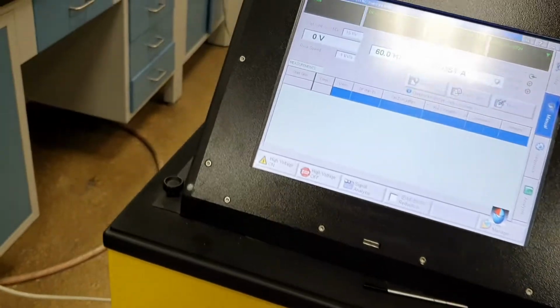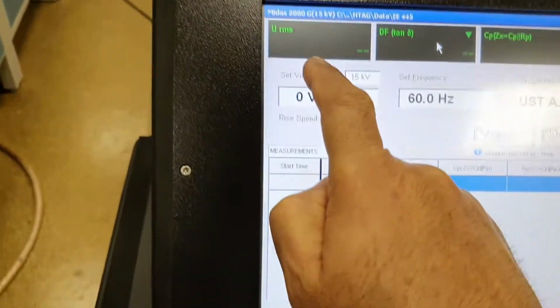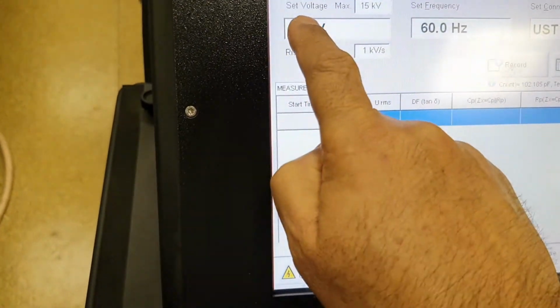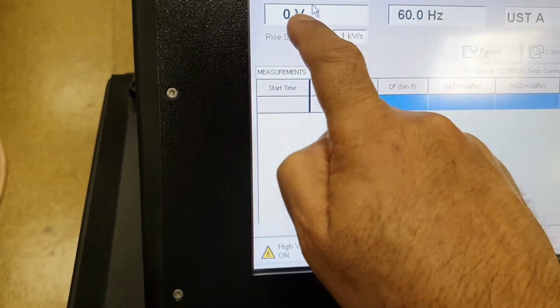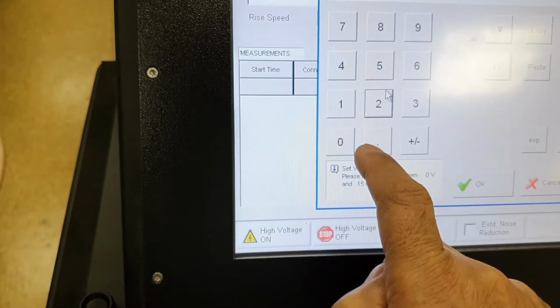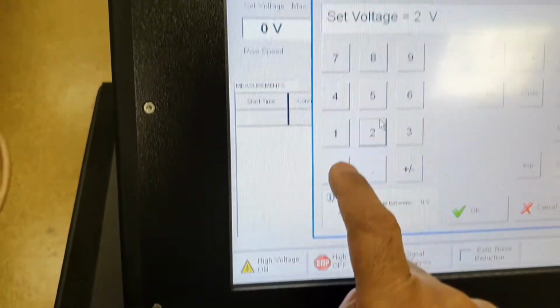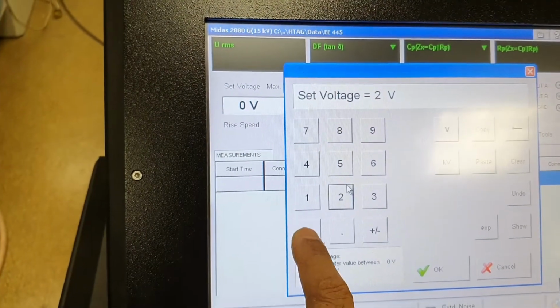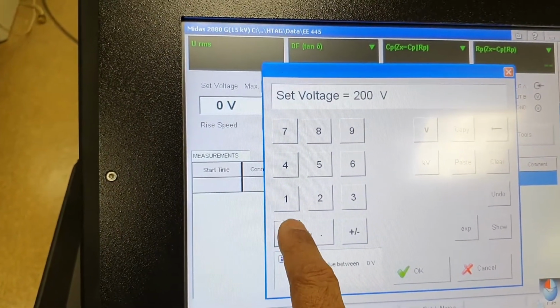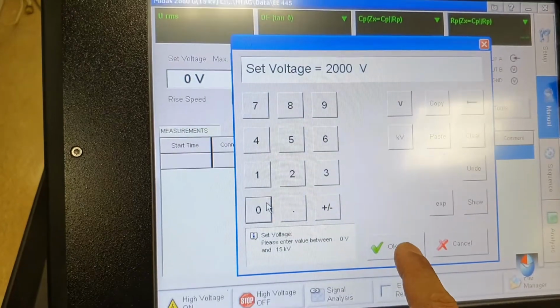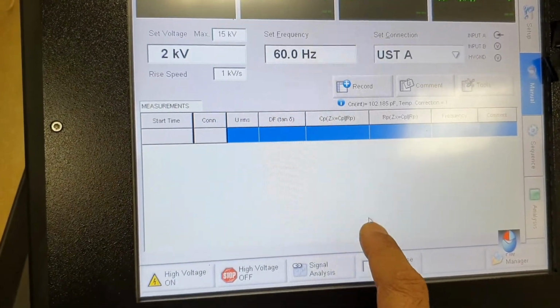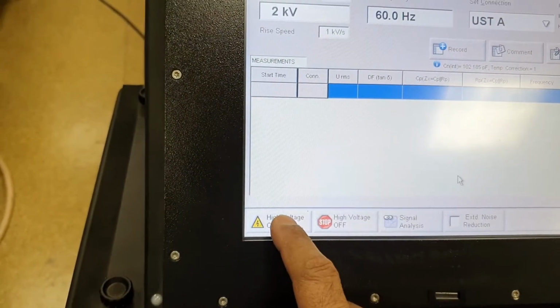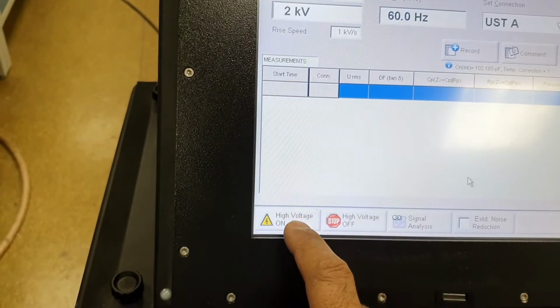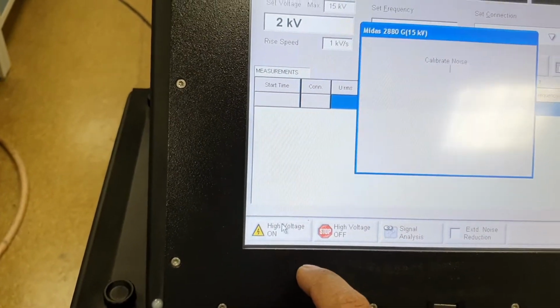You should not go beyond this control system once you energize it. Once you press it, you can select the voltage using the finger touch panel. We'll be doing this at 2 kilovolts, so enter 2000 and press OK.